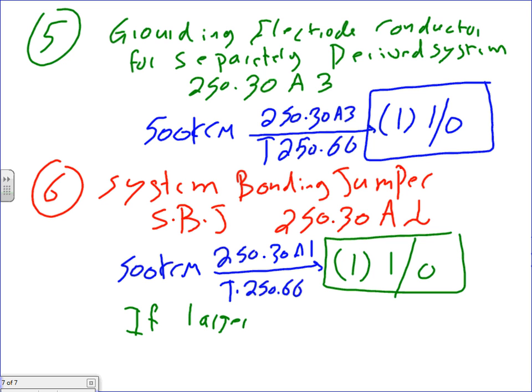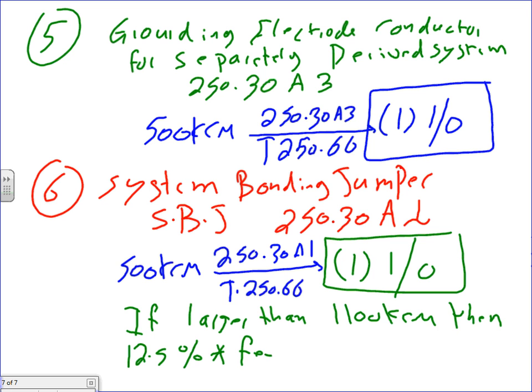Next to it, guys, if larger than 1100 kcmil, then 12.5% times the feeder conductors. Everybody can understand what I wrote here, guys? So 1 aught, but if the feeder was larger than 1100 kcmil, then you have to take 12.5% times the feeder conductor size. Write yourself this note that will keep you energized for the rest of your life.